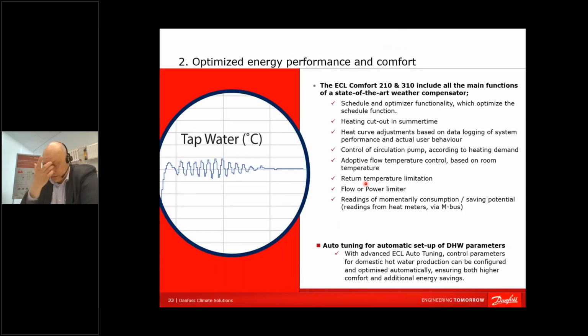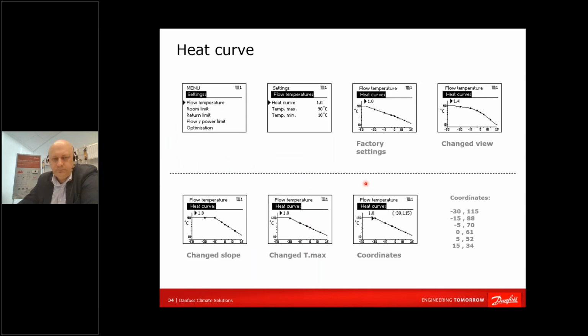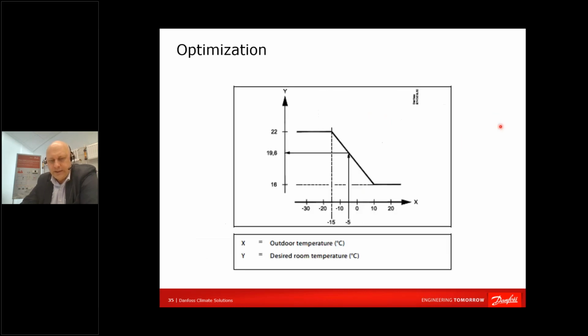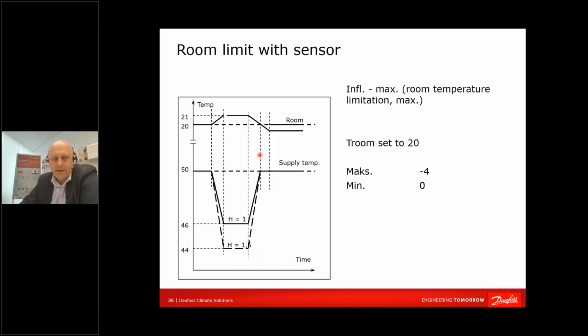See controls. Optimized controller. How do we control it? So we might change the heating curve to desired value with 6 breakpoints. We can have an outdoor temperature dependent saving. So the colder it gets, the less we are reducing temperature to the heating system. If we're utilizing room temperature sensors, we have 2 solutions which we can utilize, like a maximum limitation. So if your room temperature is getting 1 degree higher, we can limit temperature depending on the settings.